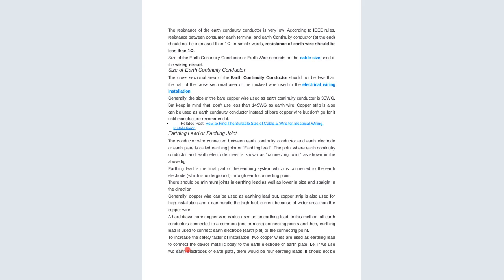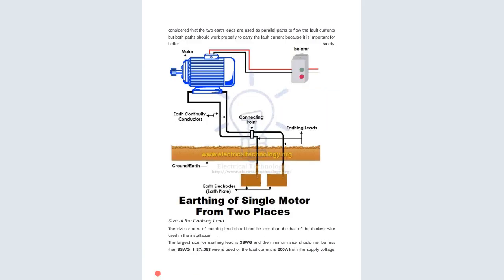To connect the device metallic body to the earth electrode or the earth plate, if we use 2 earth electrodes for the earth plate, there would be 4 earthing leads. It should not be considered that the 2 earth leads are used in parallel paths to carry the fault currents, but both paths should work properly to carry the fault current because it is important.